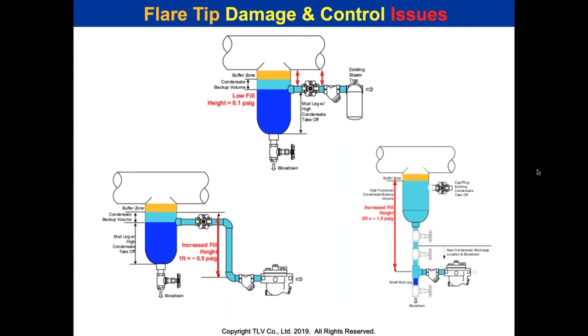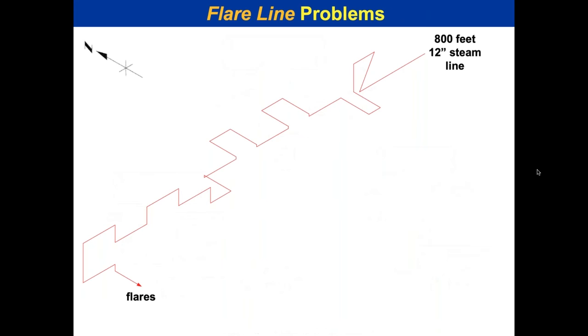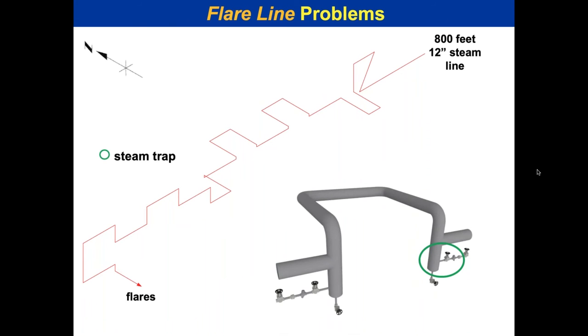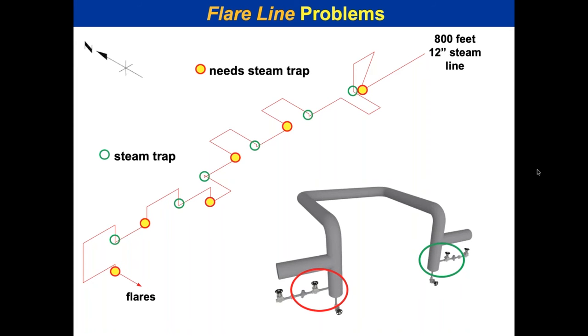It's much better if you're on the projects team to ensure proper collecting leg design — not only the D1 distance but the L distance. We walked an 800-foot section of 12-inch flare line, mapped where steam traps existed — six traps — but identified six additional locations where traps were needed. Isn't it worthwhile to add six traps to your flare line to make your flare system that much more reliable?